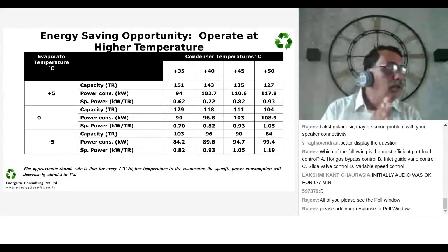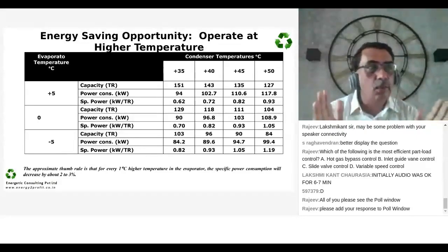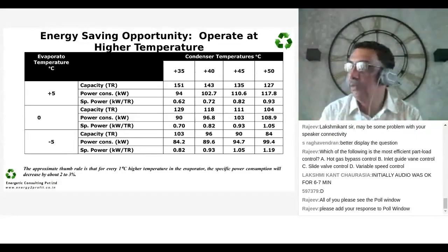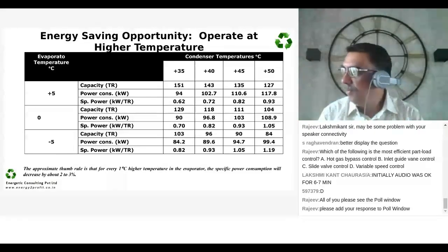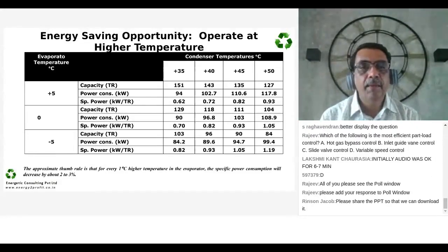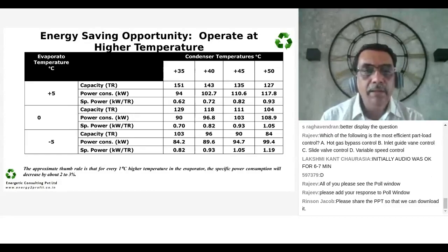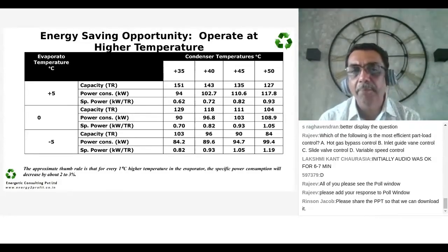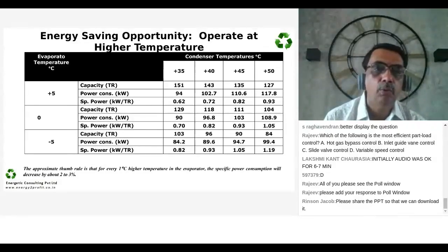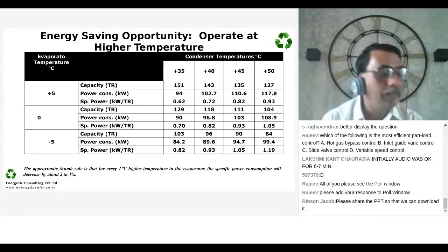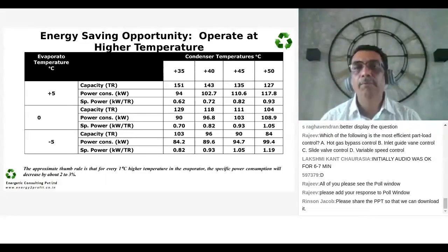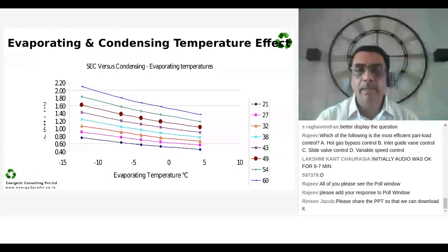when you are using chilled water. This is called the approach. The difference between these two temperatures is the approach. So the thumb rule is, for 1°C higher temperature in the evaporator, the specific power consumption will reduce by about 2 to 3%. Okay, this is the thumb rule.